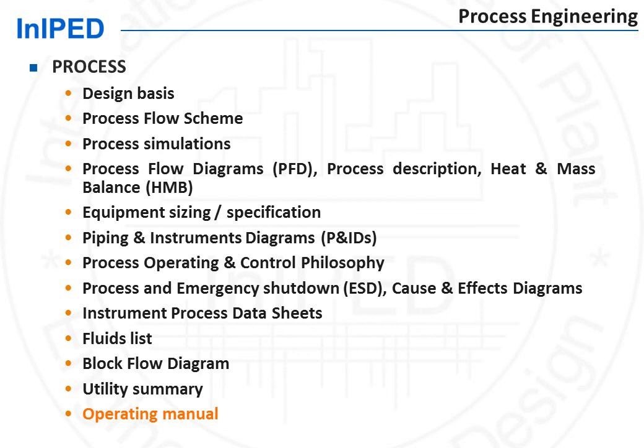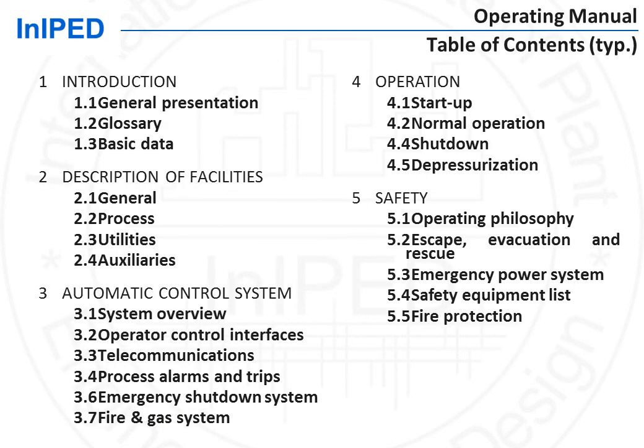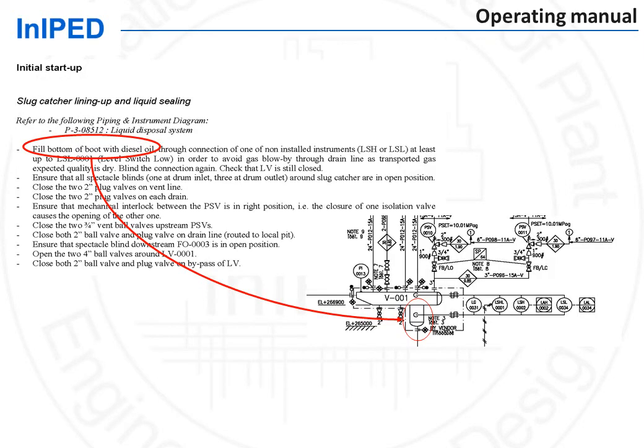The final activity of the process engineer is to issue the plant operating manual. The operating manual contains, first of all, a description of the facility. It contains a special focus on the process control system, which is the interface between the operator and the plant. It naturally contains detailed instructions for startup, normal operation, as well as shutdown of the plant. It also contains reference information, such as the capacity of the various vessels and equipment, the set points of controllers, alarms.